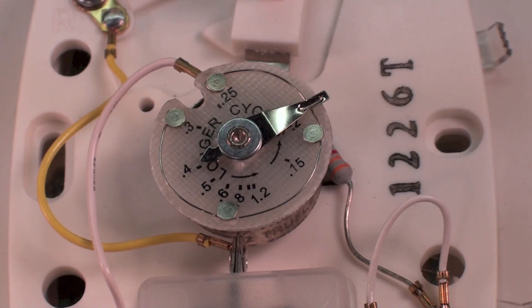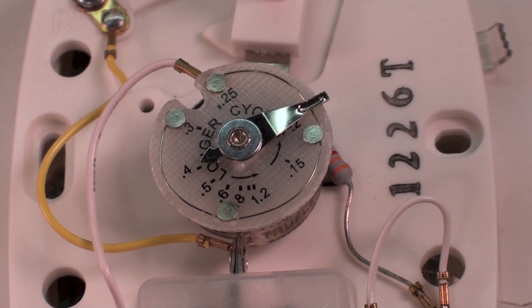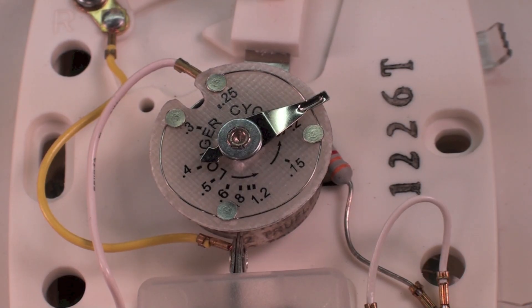So those are a few little tips on that if you don't have a meter. Just a quarter inch at a time - longer cycles means it's too hot, too cold. Shorter cycles means it's running really short periods of time and perhaps not catching up to temperature when it runs. And that's it on adjusting the anticipator without a meter.